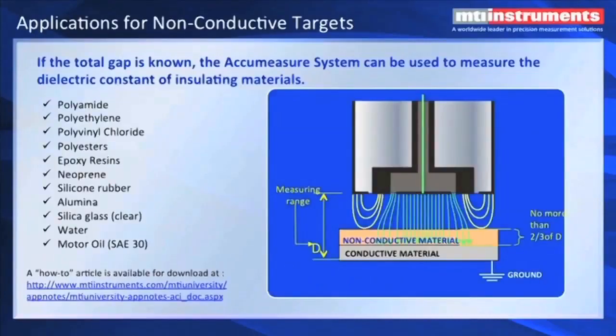MTI can also measure non-conductive targets. There's a dielectric constant associated with dielectric targets, and if you know what that dielectric constant is, you can, if you insert this material in the gap between a probe at a fixed gap where you know the height of the probe above a conducting metal target, you can measure the thickness of the non-conductive material. We also, if you look at our website, we have a number of formulas and techniques for figuring out what the dielectric constant is of your material and how to set your probes up to make this measurement. It's a little bit tricky, but it's possible to do it.